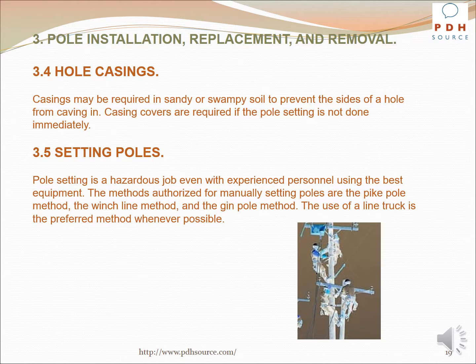Casings may be required in sandy or swampy soil to prevent the sides of a hole from caving in. Casing covers are required if the pole setting is not done immediately. Pole setting is a hazardous job even with experienced personnel using the best equipment. The methods authorized for manually setting poles are the pike pole method, the winch line method, and the gin pole method. The use of a line truck is the preferred method whenever possible.